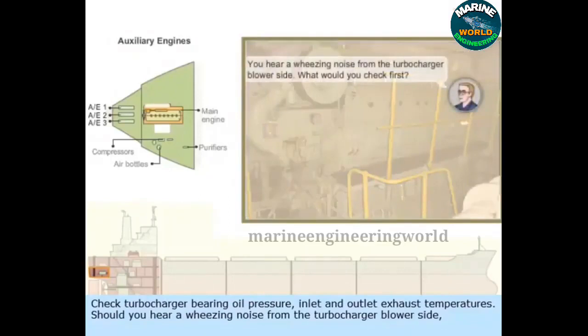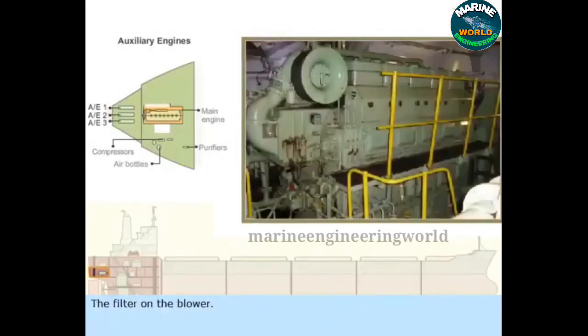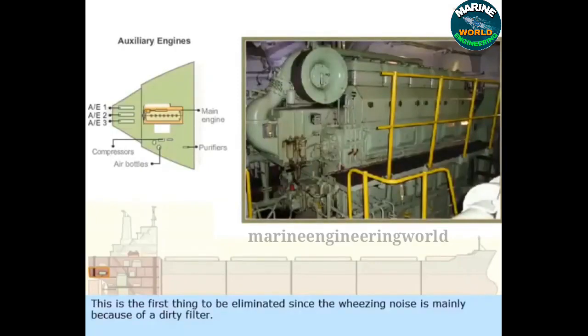Should you hear a wheezing noise from the turbocharger blower side, what would you check first? The filter on the blower. This is the first thing to be eliminated since the wheezing noise is mainly because of a dirty filter.